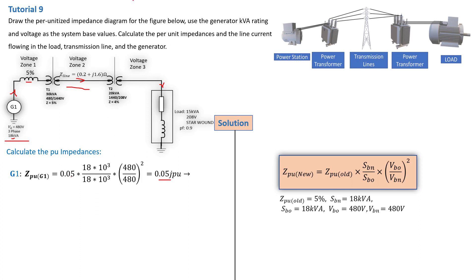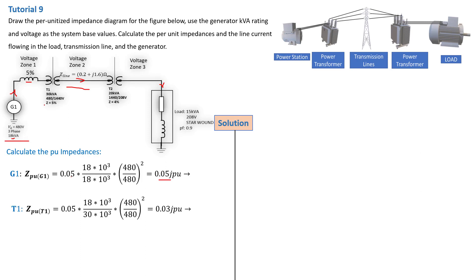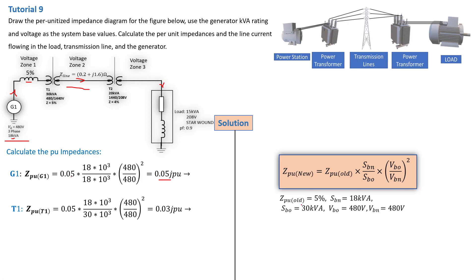Moving on to transformer T1: we apply exactly the same general formula. Z per unit old for T1 is 5%, SB_new is 18 kVA, SB_old is 30 kVA, VB_old is 480 V, and VB_new is 480 V because the new voltage comes from the generator and the primary of the transformer is exactly the same. Substituting these values gives us Z_T1 = 0.03 per unit.